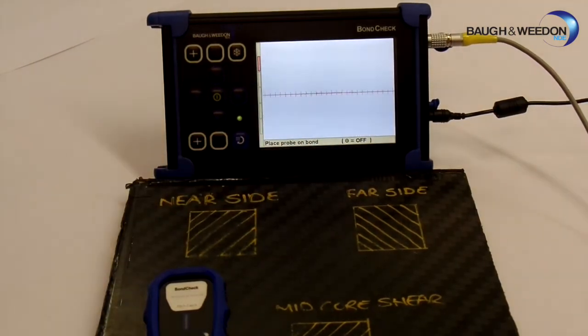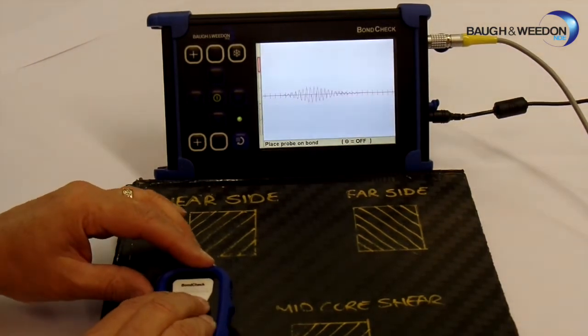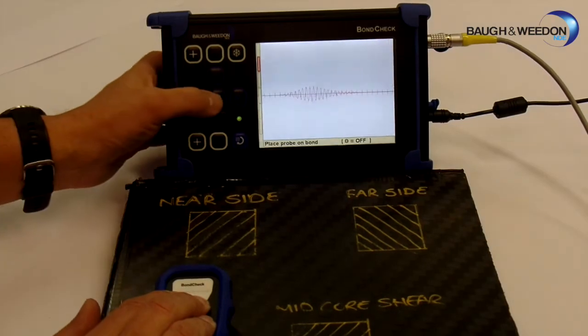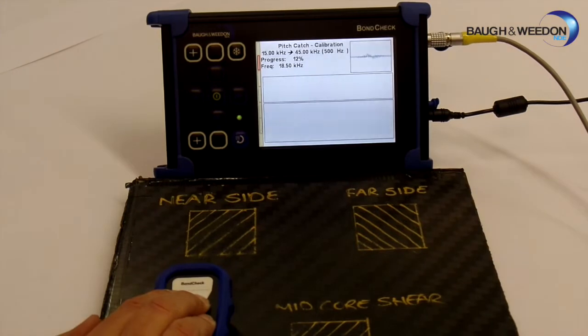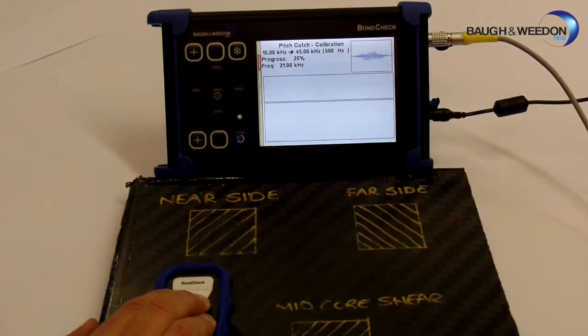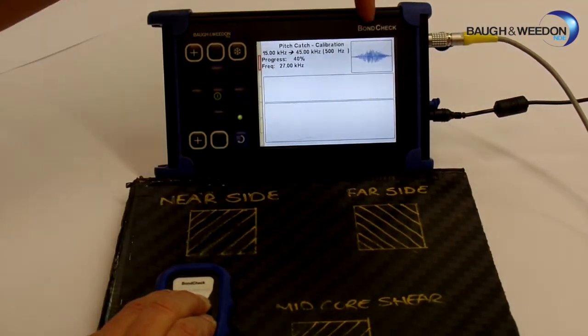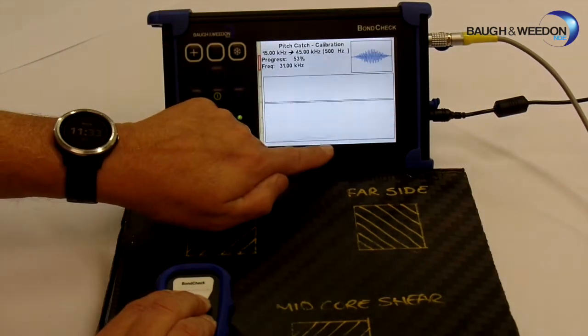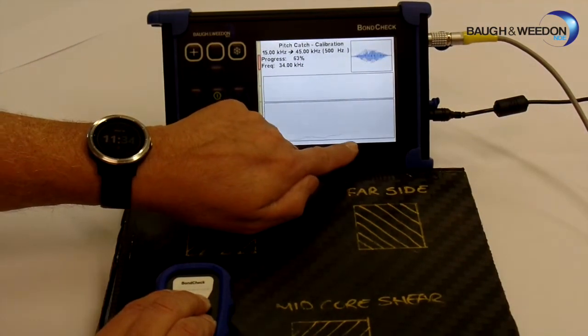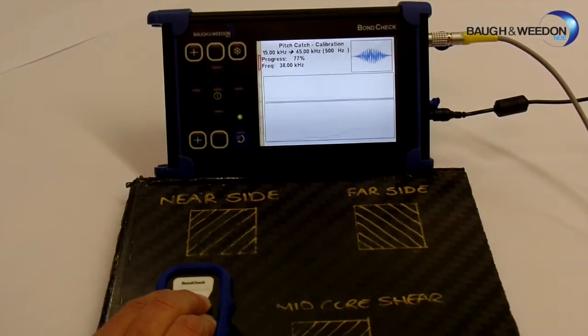And what it says down here is place probe on bond. What that means is place the probe on a bonded area, so on the test piece. So we know this area is bonded, so we position it, put it down, press the green button, and it will now ramp through the frequencies that we have selected. Instantaneous frequency response there, and this is the amplitude slowly crawling across the screen as it goes through each of the different frequencies that we have selected.